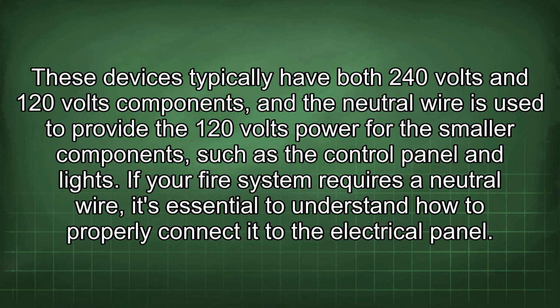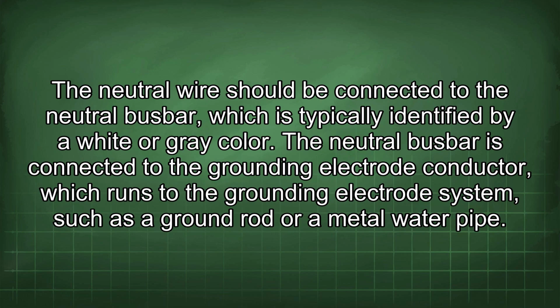These devices typically have both 240-volt and 120-volt components, and the neutral wire is used to provide the 120-volt power for the smaller components, such as the control panel and lights. If your fire system requires a neutral wire, it's essential to understand how to properly connect it to the electrical panel. The neutral wire should be connected to the neutral busbar, which is typically identified by a white or grey color. The neutral busbar is connected to the grounding electrode conductor, which runs to the grounding electrode system, such as a ground rod or a metal water pipe.